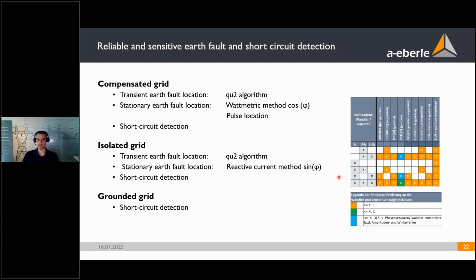This method does not have such high requirements for measurement accuracy. So in an isolated grid, the requirements for measurement accuracy are lower than in a compensated grid. And you have short circuit detection as well. And in the grounded grid, you only have short circuit detection since the earth fault would be a short circuit as well.